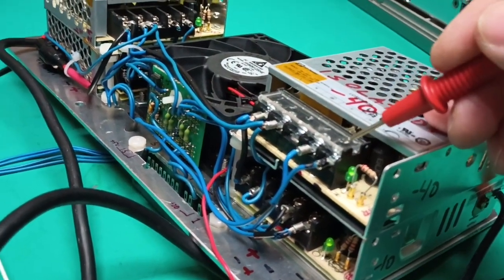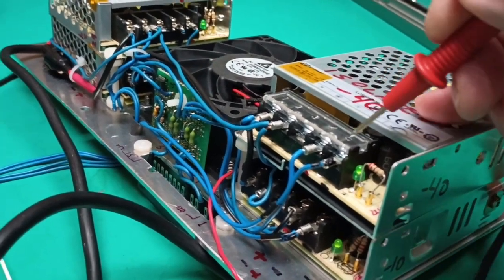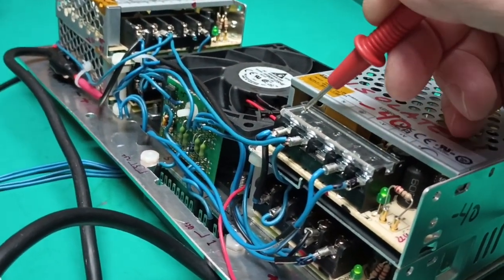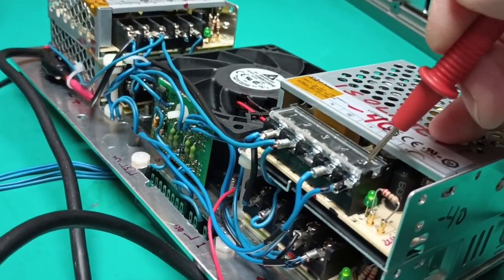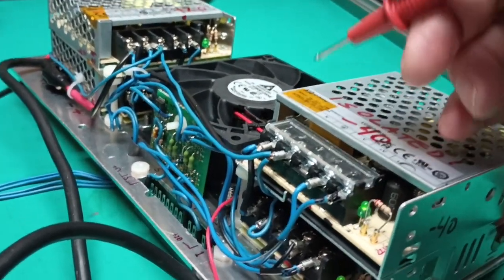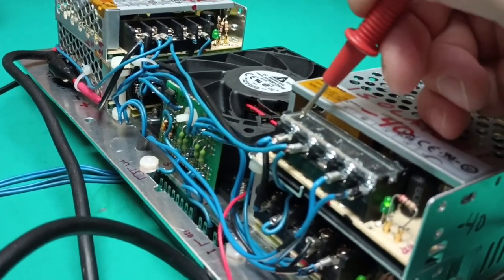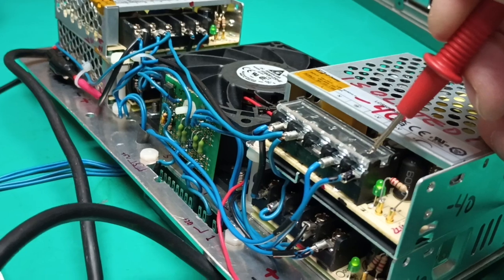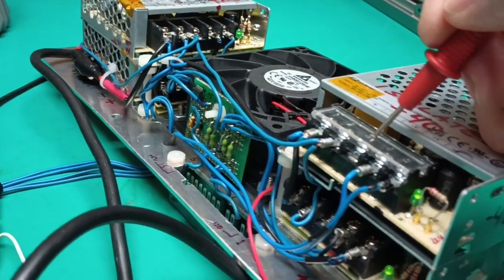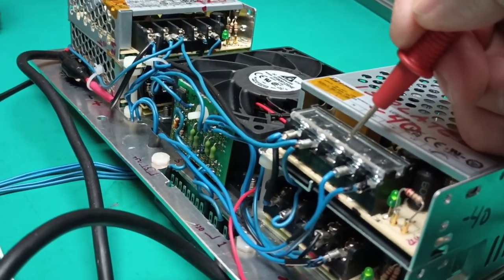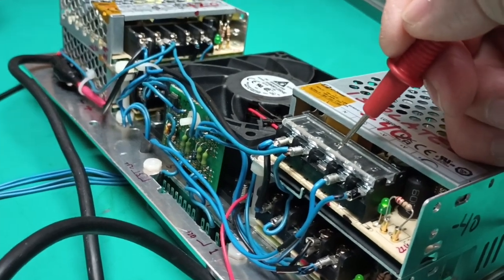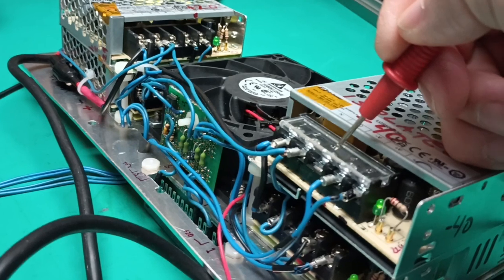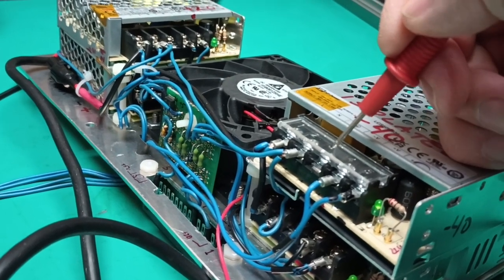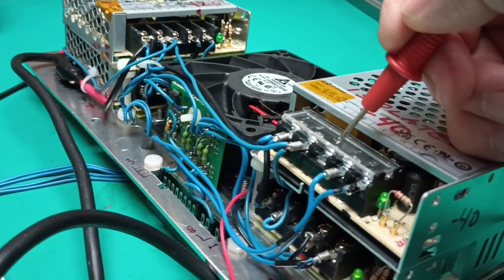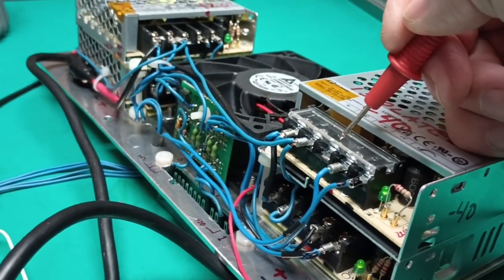So that's why those strange readings appear everywhere. They're all connected together. All four of these except L1 are all connected together inside by disc ceramic capacitors. And L1 is eventually connected to all these through leakage. And so-called commoning, it's not grounding, but commoning this so-called earth terminal allows that current to be drained off effectively. So those voltage drops disappear.